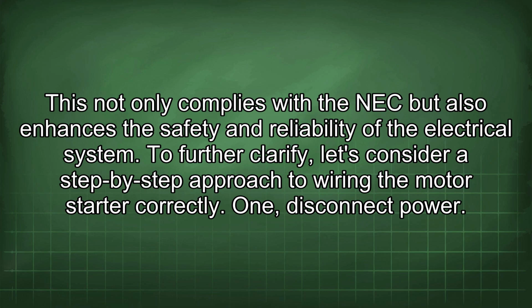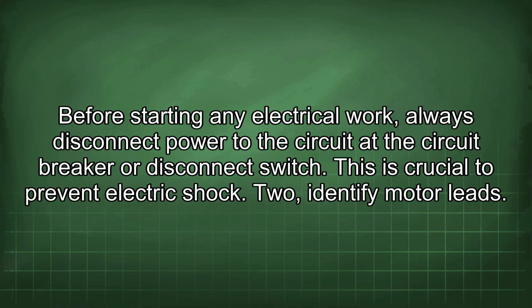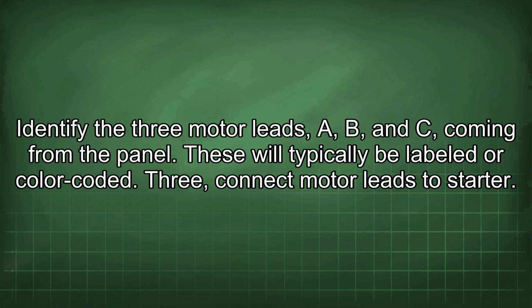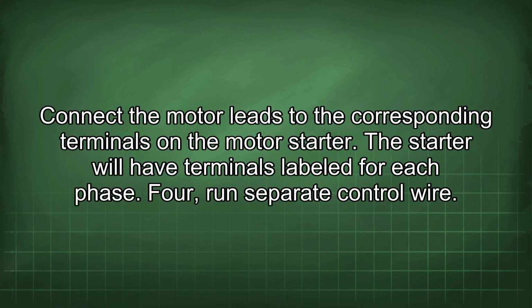To further clarify, let's consider a step-by-step approach to wiring the motor starter correctly. 1. Disconnect power. Before starting any electrical work, always disconnect power to the circuit at the circuit breaker or disconnect switch. This is crucial to prevent electric shock. 2. Identify motor leads. Identify the three motor leads A, B, and C coming from the panel. These will typically be labeled or color-coded. 3. Connect motor leads to starter. Connect the motor leads to the corresponding terminals on the motor starter. The starter will have terminals labeled for each phase.